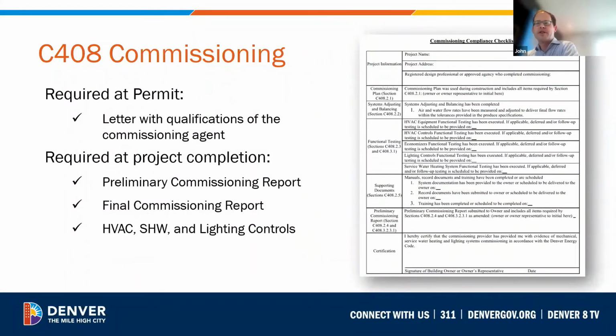The commissioning compliance checklist documents the commissioning process. It summarizes the results of the process not only for HVAC, but also for lighting and service water heating. Typically, before functional testing, a test and balance or TAB contractor performs testing and adjustment of the airflows and water flows for all major equipment to ensure that systems operate as intended on the construction drawings. A letter shall be provided with the qualifications of the contractors performing commissioning with the permit documents.